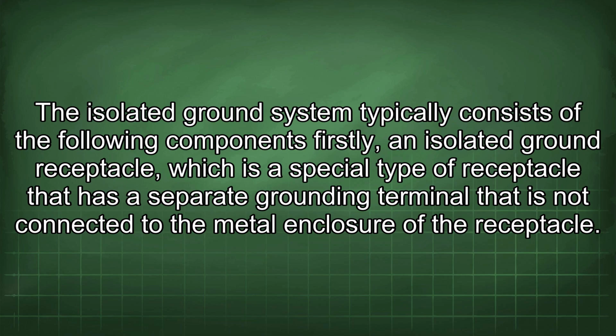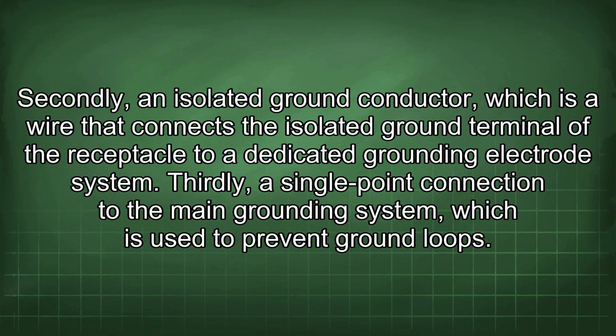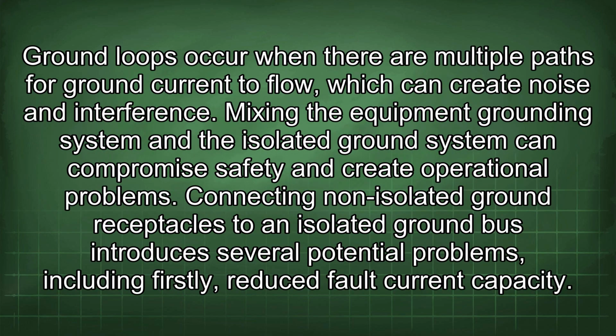The isolated ground system typically consists of the following components. Firstly, an isolated ground receptacle, which is a special type of receptacle that has a separate grounding terminal that is not connected to the metal enclosure of the receptacle. Secondly, an isolated ground conductor, which is a wire that connects the isolated ground terminal of the receptacle to a dedicated grounding electrode system. Thirdly, a single-point connection to the main grounding system, which is used to prevent ground loops. Ground loops occur when there are multiple paths for ground current to flow, which can create noise and interference.